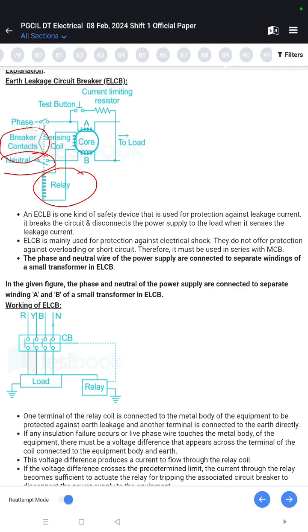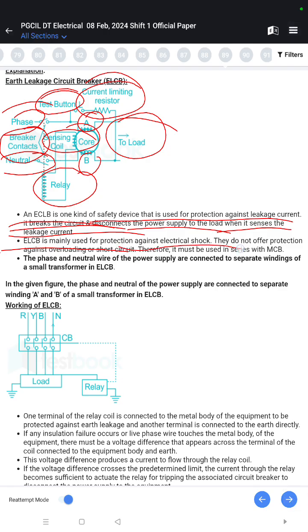Relay, neutral, breaker contact, phase, test button, current limiting resistor, to load, A-B, core, sensing coil. An ELCB is one kind of safety device that is used for protection against leakage current. It breaks the circuit, disconnects the power supply to the load when it senses the leakage current. ELCB is mainly used for protection against electrical shock. They do not offer protection against overloading or short circuit, therefore it must be used in series with MCB.